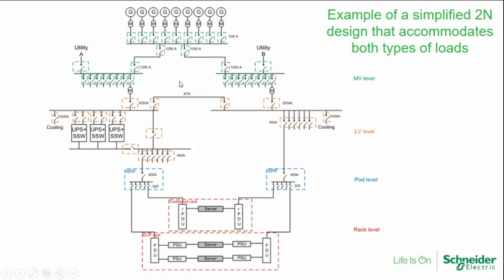Right-sizing all the components, only putting what's necessary. This is a 2N design, which is the most typical architecture for enterprise data centers and co-location, but the UPS system is only on one side. You still have two paths and can do concurrent maintainability, but your battery backup is on one side, which optimizes cost and increases efficiency by keeping components running at a good load. At the bottom we're demonstrating how you can have traditional servers fed off regular circuits and off the same RPP alongside open compute racks.